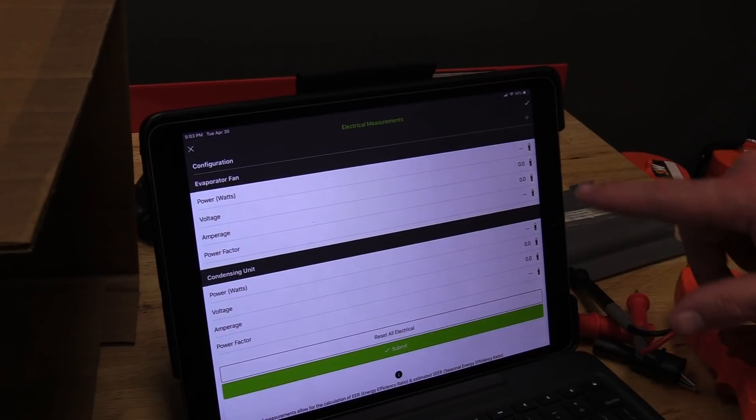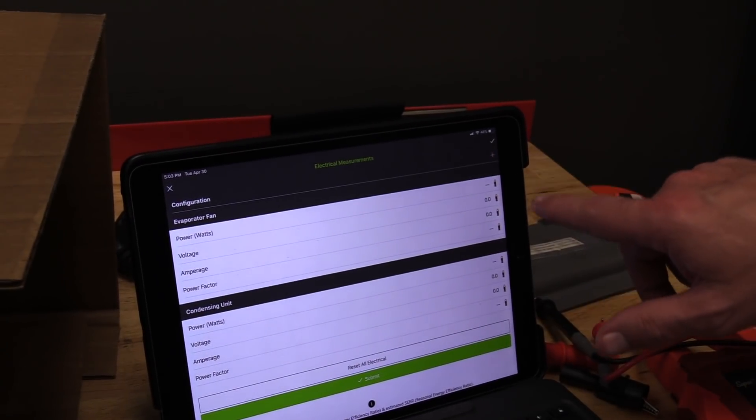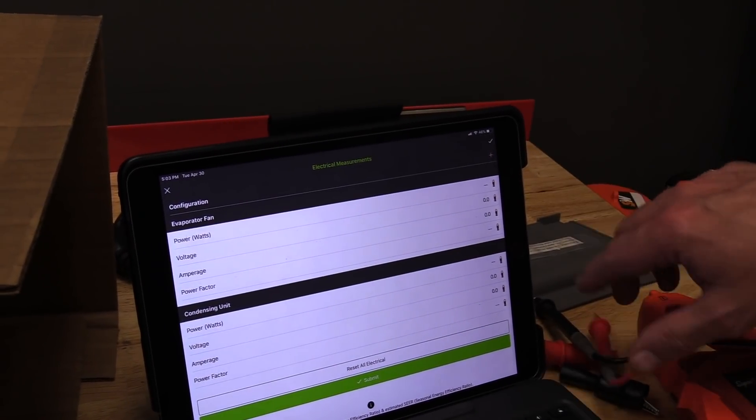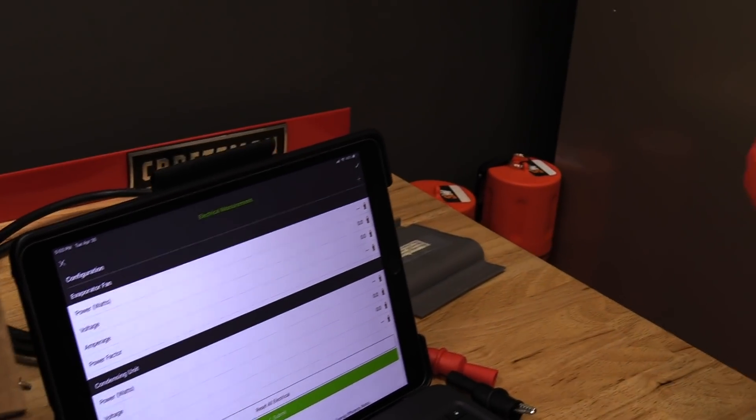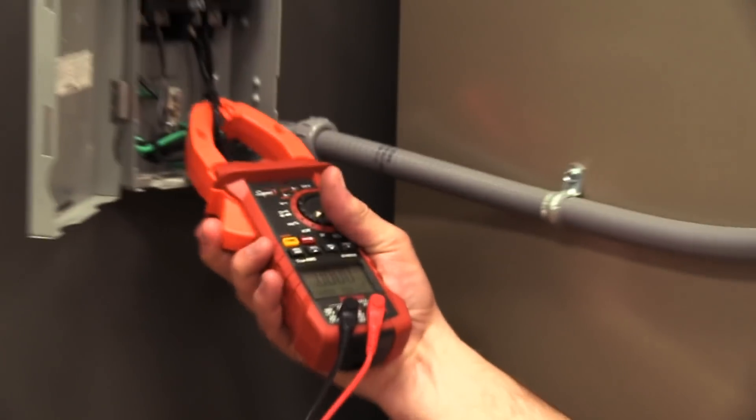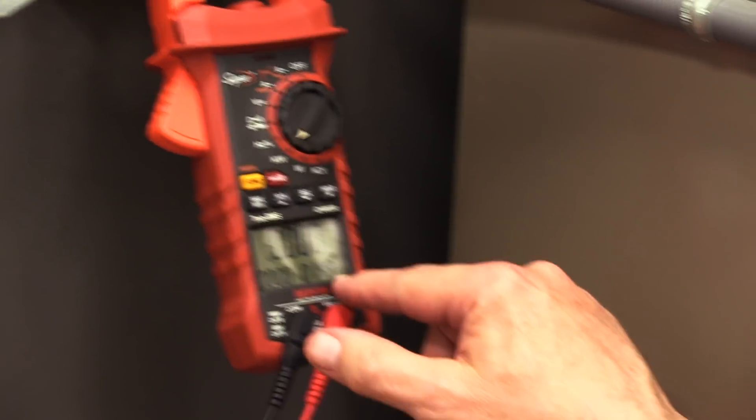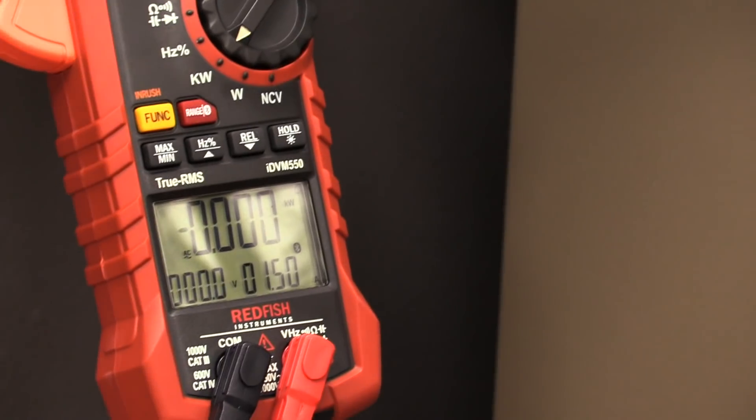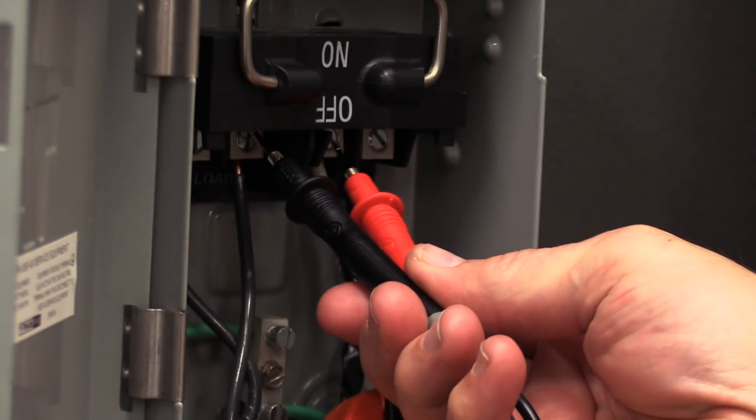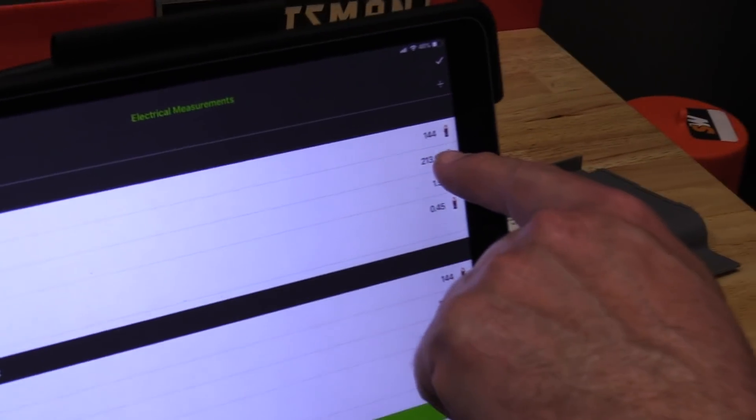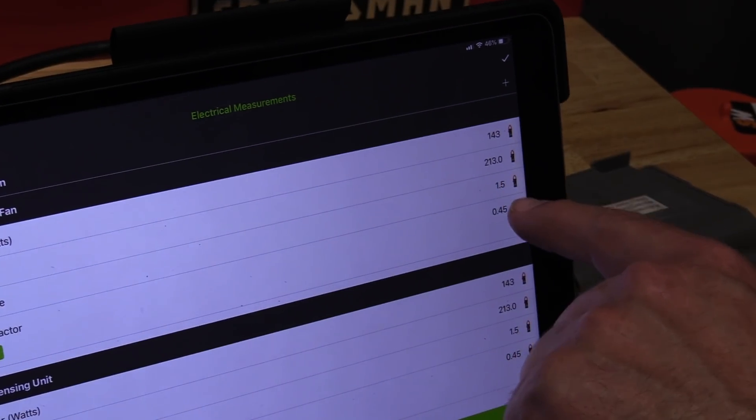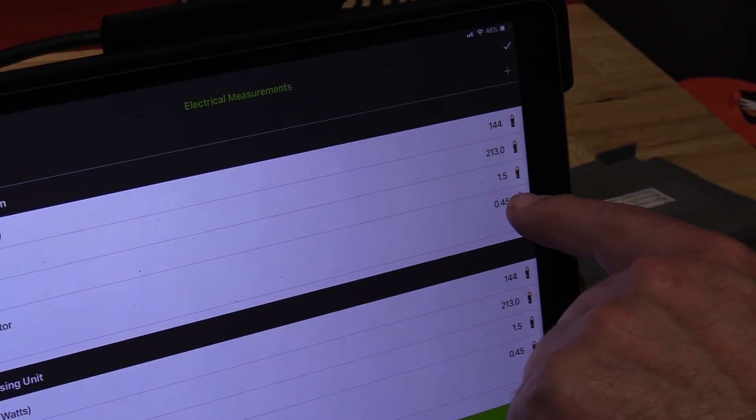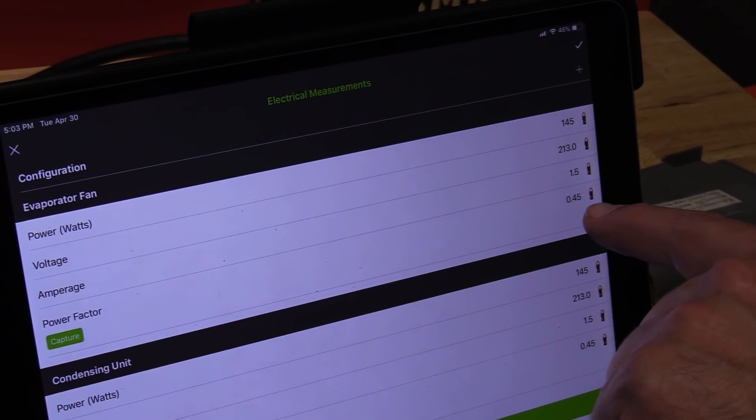As soon as it picks up that the meter's attached, it automatically goes into watt mode. I'm going to clamp around one of the legs of the 240. You can see we're drawing 1.49 amps. Then I'm going across the load side of the contactor. As soon as I go across the load side, there's our power in watts, our voltage of 213, our amperage 1.5, and our power factor 0.45. I'll just hit capture on that.